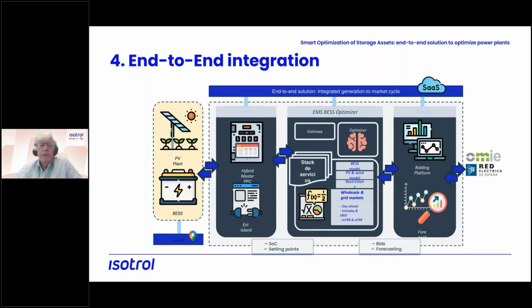Google Maps tells us which is the best route, but the one who is driving here in the plant is the control system and the PPC, the power plant controller of the plant. So the optimizer sends an optimal plan, but if the plant has to change because, say, the results have changed, or there is a restriction, a command from the TSO or whatever, it changes its behavior. In this case, the optimizer gets this information and reacts, generating a new planning, a new optimal planning.